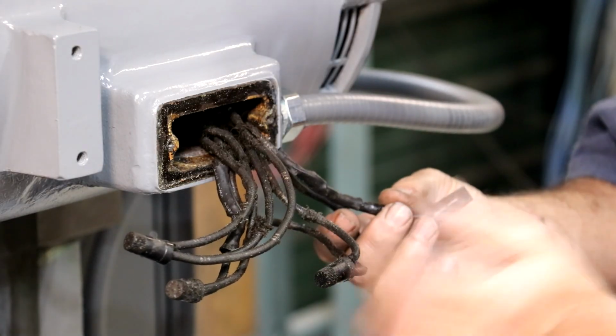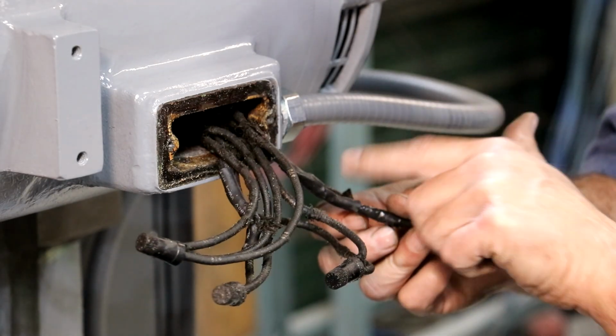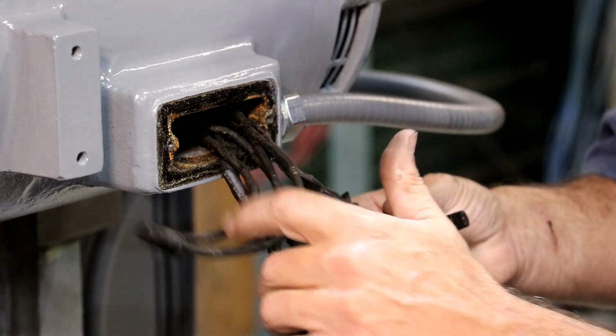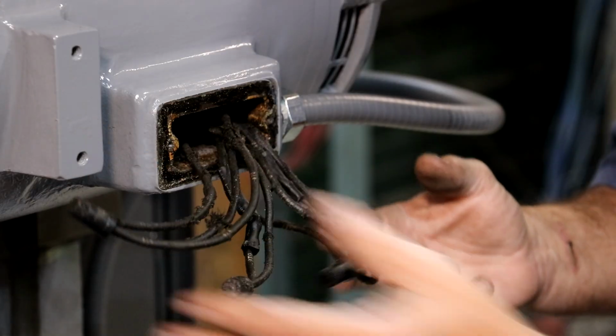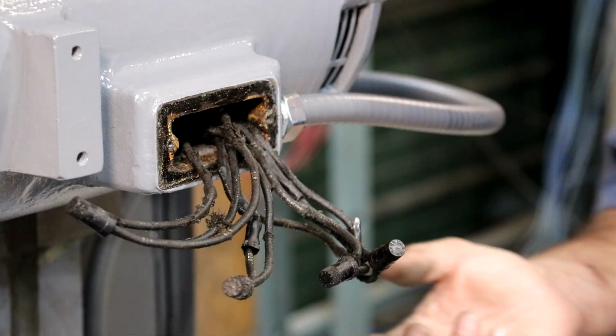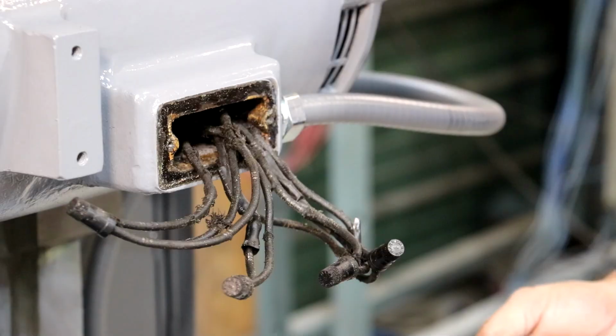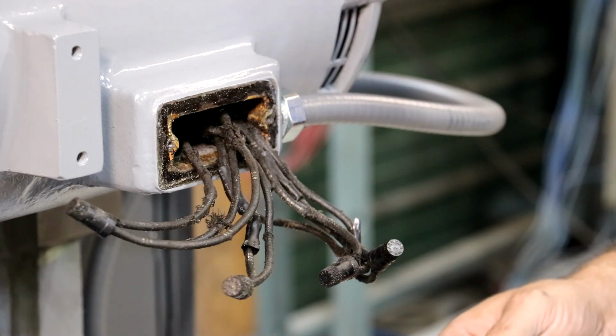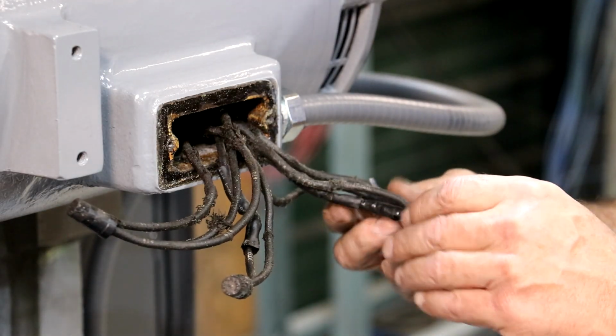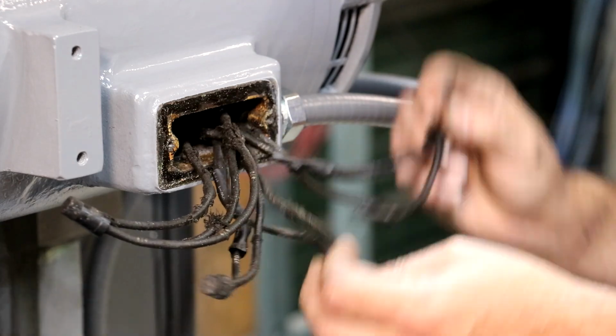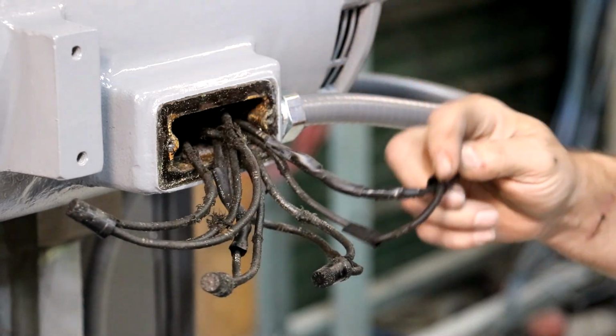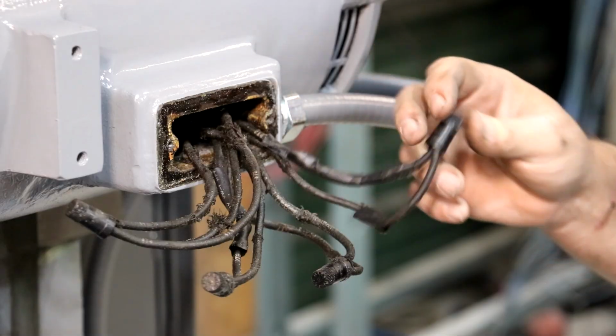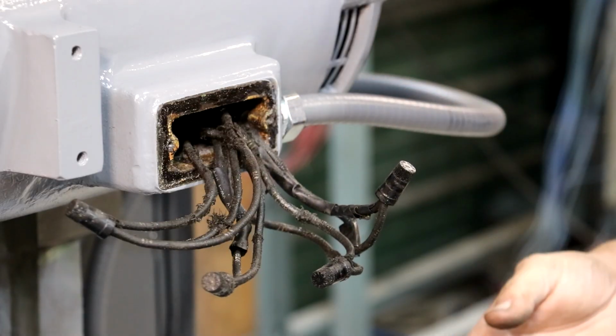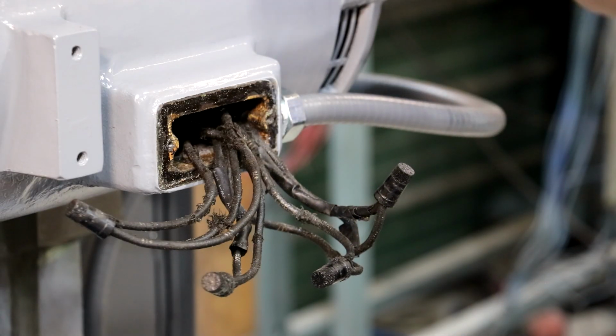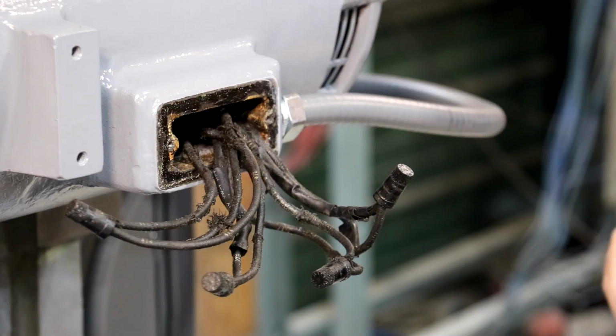These are the wires that come out of the motor. There's 1 through 9 leads coming out, which is typical on a 3-phase motor. If it's a dual voltage motor, you'll have 9 leads coming out, and depending on how you tie these leads together, you get the option to run the motor at low voltage, 220 volts, or high voltage, 440 volts. Obviously we're running on 440 volts in this situation.